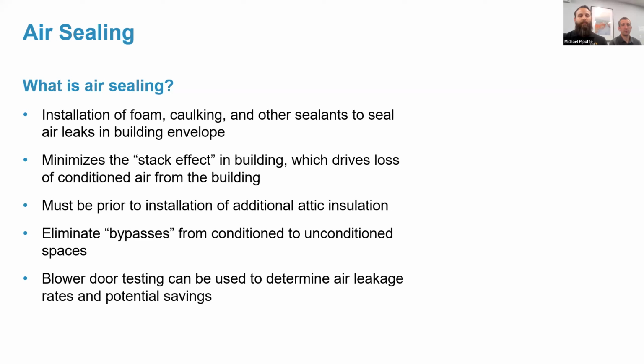It is important to note that before doing any insulation, the air sealing should be addressed so that you can get the best possible access to the different components of the building where the air is traveling and bypassing the intended thermal boundary. For smaller facilities, I know always in residential buildings, but in some small commercial buildings, some blower door testing can be used to determine the existing air leakage and ensure that any air sealing that is done doesn't over seal the building, because while you do want to minimize air leakage in a building, you don't want to completely seal it.